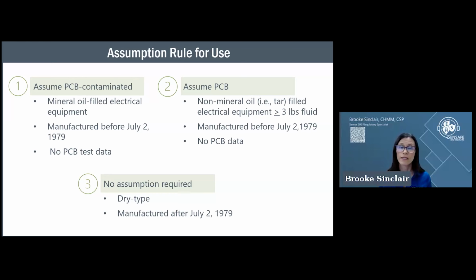Remember, that's 50 to 499 parts per million. If you have non-mineral oil, meaning tar-filled electrical equipment with 3 pounds of fluid or more—which is hard to know, so rule of thumb, if you think it has tar in it—and it was manufactured before July 2nd, 1979, with no PCB data, you assume it's PCB, meaning 500 parts per million or greater.